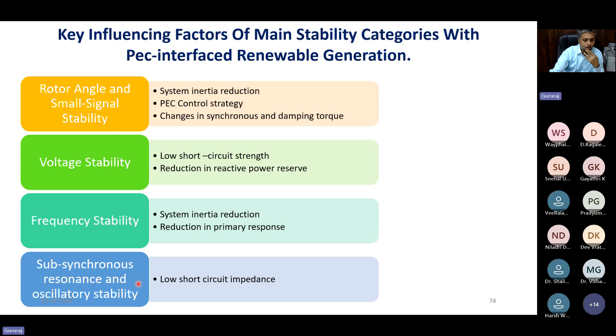Then there are voltage stability issues like reduced reactive power reserve, and frequency stability issues because of inertia issues and reduction in primary response, and subsynchronous resonance, and oscillatory stability issues. This is there with the wound-rotor induction machine also - SSR. I hope you're all familiar with SSR issues because of series capacitors, where resonance takes place resulting in low short circuit impedance, which is a challenging point.